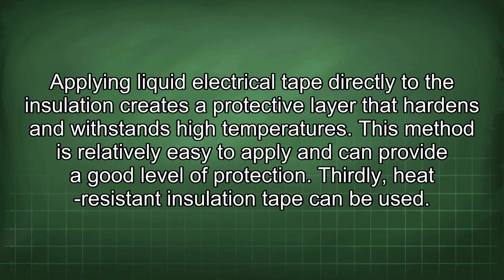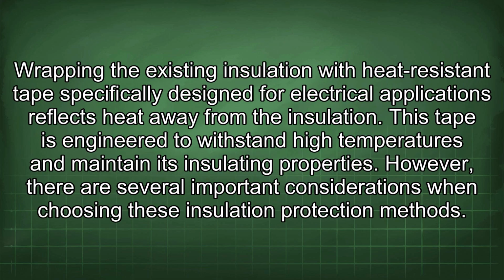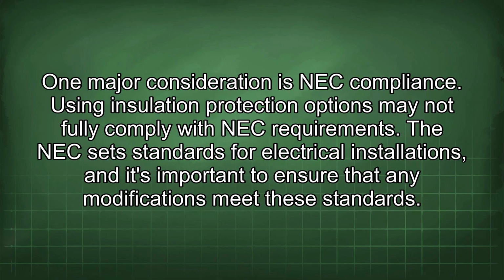Thirdly, heat-resistant insulation tape can be used. Wrapping the existing insulation with heat-resistant tape specifically designed for electrical applications reflects heat away from the insulation. This tape is engineered to withstand high temperatures and maintain its insulating properties. However, there are several important considerations when choosing these insulation protection methods. One major consideration is NEC compliance. Using insulation protection options may not fully comply with NEC requirements. The NEC sets standards for electrical installations, and it's important to ensure that any modifications meet these standards.